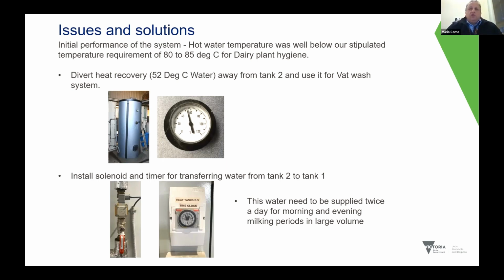So we then installed a solenoid valve and a timer to divert that tank 2 water into tank 1. And this water needed to be supplied twice a day for morning and evening milking periods in large volumes. We also found that having the system ready for 10 hours, the guys before described a well-insulated tank. The tanks are well-insulated, but there is a temperature loss, whether it be 2 to 5 degrees, that we noticed just looking at our data logger. So we made sure that we turned on the system just before we required the hot water, about 4 hours before the milking period started.